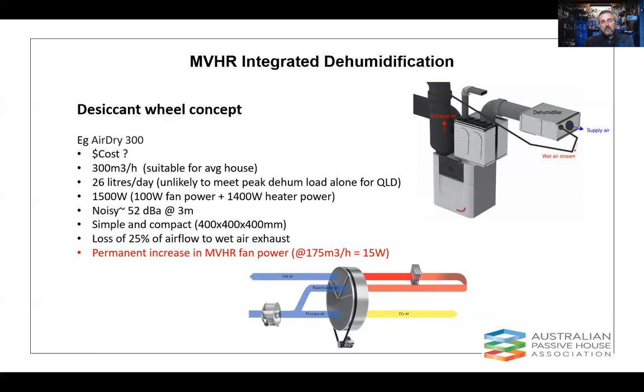But relatively compact, because that wheel's compact and the heater can be small, it can fit into a fairly small location. What we do suffer is a loss of some airflow out of these. So that airstream that takes away that moist air is actually lost supply air. So we're going to lose potentially up to 25% of our airflow to what they call the wet air exhaust.